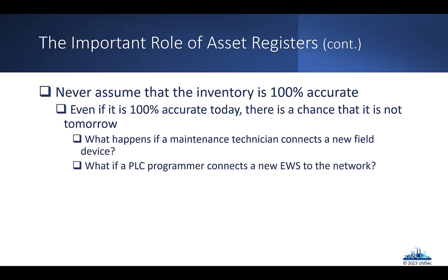We can look at what if a PLC programmer brings in a new engineering workstation — maybe a new laptop — and it wasn't processed through the appropriate change control processes. It doesn't necessarily mean there's a true cybersecurity threat; it's not an attacker, just somebody trying to get their job done. But we want to make sure those assets are added correctly to the environment so we know about them and can keep them secure. We want to make sure that engineering workstation is hardened before the PLC programmer uses it to upload a project file to a PLC.